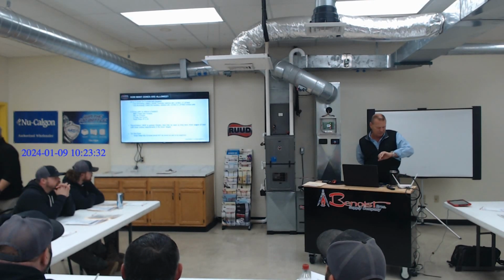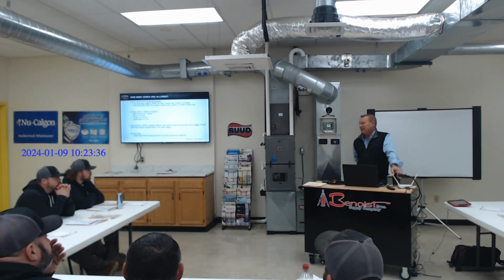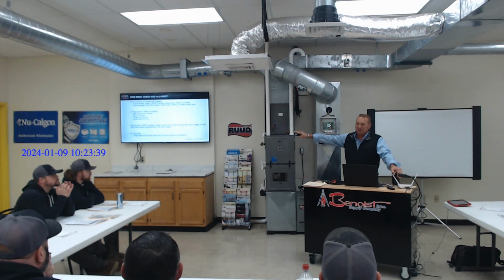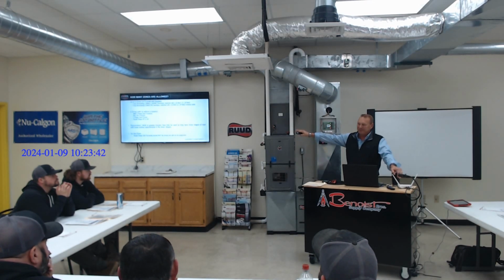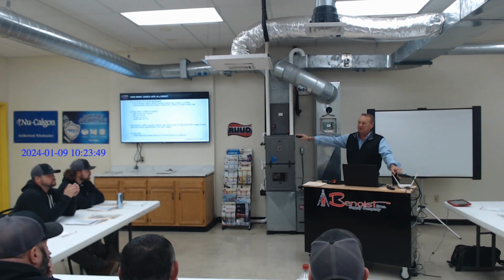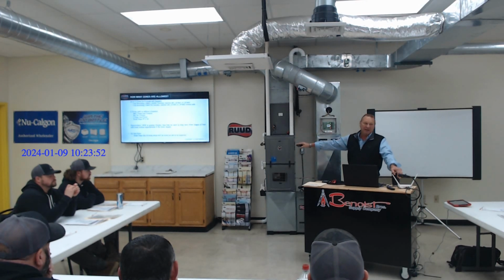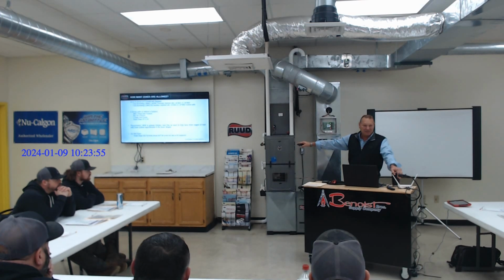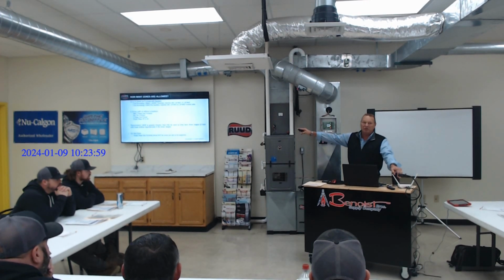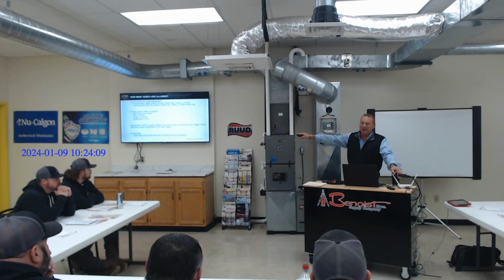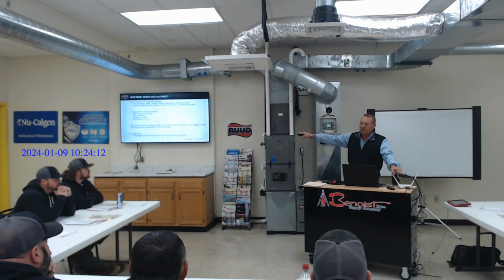So just a reminder, first of all, we can't communicate with any of our single-stage product, but the only way I'd zone single-stage is if I got monster zones and I can dump air, because all of today's zoning is about the indoor motors and CFM now. We have to get that ingrained. It's not about size of equipment as much as it is about CFM, static pressure, and what these motors can handle in the smallest zone. That's why they don't want any single-stage equipment, because everything in our single-stage furnaces is constant torque motors. And we've taken a constant torque motor into our mid-tier lines, and it's communicating unlike the old constant torques.